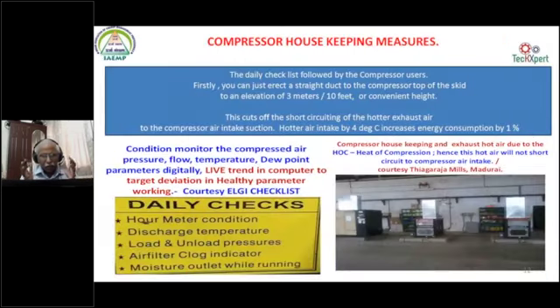So the compressor house, where housekeeping can be done. Thanks to the OEM, the daily checks are there. Are we monitoring the daily checks? The hour meter, the loaded hours and the unloaded hours. It has to be bifurcated as loaded hours and unloaded hours. The discharge temperature of the compressed air is more important. It is mentioned here, but none of us have it on the air receiver. A temperature gauge on the air receiver will show the health of the compressor. Then the load and unload pressures and the air filter clog indicator.